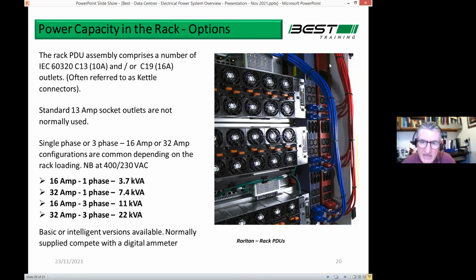And then you take a red lead and a blue lead up to every server. So every single server has an A supply and a B supply to it. They can come in single phase or 3-phase, in 16 amp or 32 amp, giving you a power range for your cabinet from anything from 3.7 kVA up to 22. And I have to say 22 kVA is getting more and more common, 22 kVA in a rack.